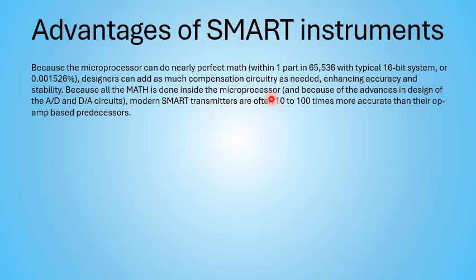So some of the advantages of smart instruments as compared to the older instrumentation we used and still do use, actually. Because a microprocessor can do nearly perfect math within our range of ability to measure, it's 1 part in 65,536 for a 16-bit system. That ends up being about 0.001526% of the span. That's pretty precise. You're probably not going to have equipment that can actually measure that small of an increment or an error.